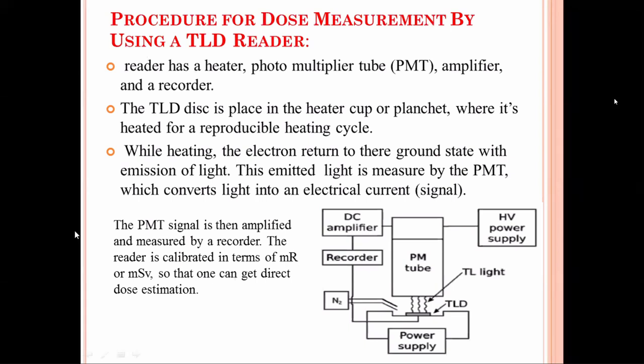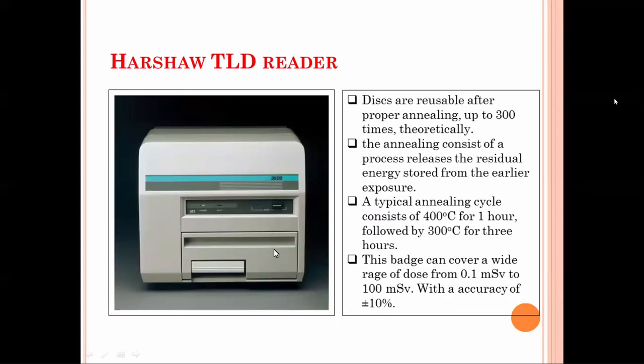The TLD reading procedure involves a DC amplifier, recorder, nitrogen gas for cooling, a photomultiplier tube (PMT), and power supply. The TLD card is placed in the reader, the system is started, and it heats to above 300 degrees Celsius, emitting light or luminescent signals. This is detected by the PMT, which transfers the signal into an electronic reading recorded as your dose. The Harshaw TLD reader is most widely used and costs around two crores.